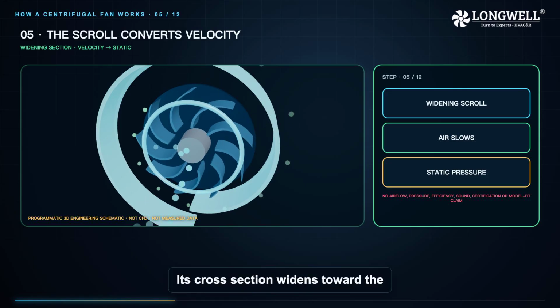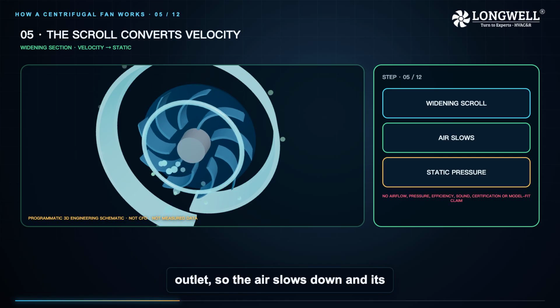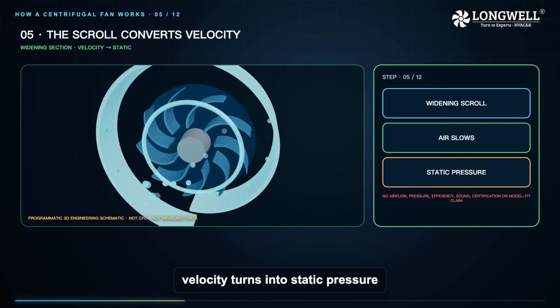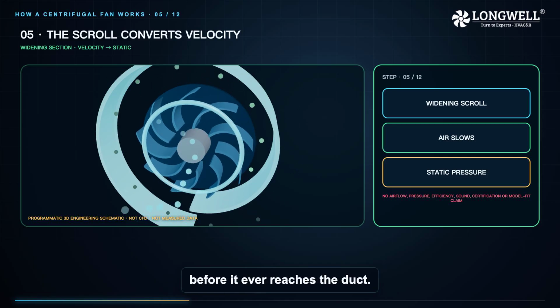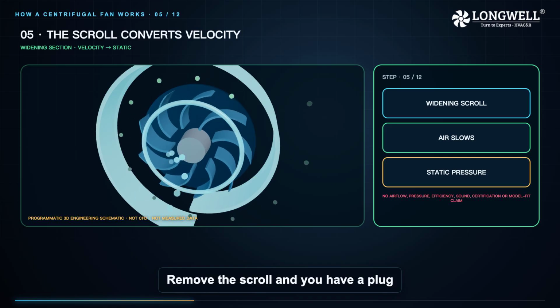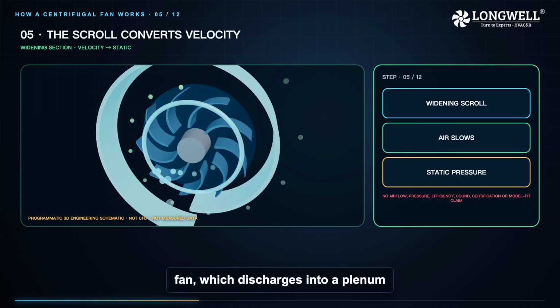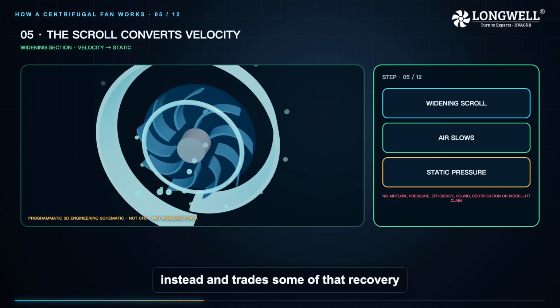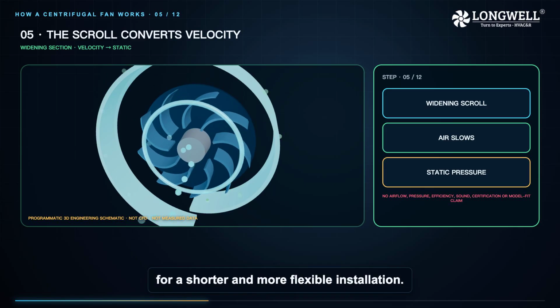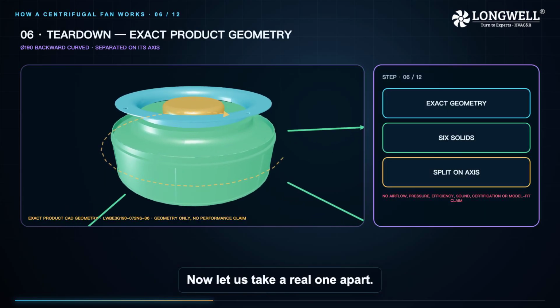Its cross-section widens toward the outlet, so the air slows down and its velocity turns into static pressure before it ever reaches the duct. Remove the scroll and you have a plug fan, which discharges into a plenum instead and trades some of that recovery for a shorter and more flexible installation. Now let us take a real one apart.